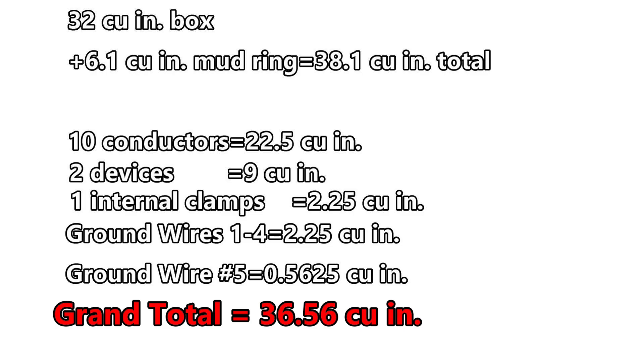So ground wires one through four get one full allowance for 2.25 cubic inches, and ground wire number five gets one quarter of one allowance — 2.25 divided by 4 is 0.5625 — giving us a grand total of 36.56 cubic inches. The box with the mud ring included is 38.1 cubic inches, so it passes. Congratulations! If you said it was going to pass, you're correct. Thank you very much and I hope this video was helpful.